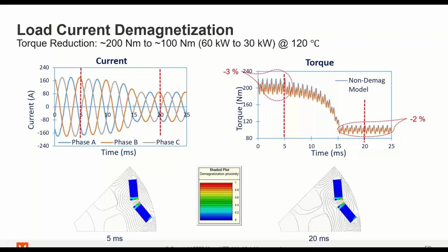And if the loss is severe, the motor would need to be replaced, since high energy magnets like NEO, for example, cannot be magnetized on the fly.